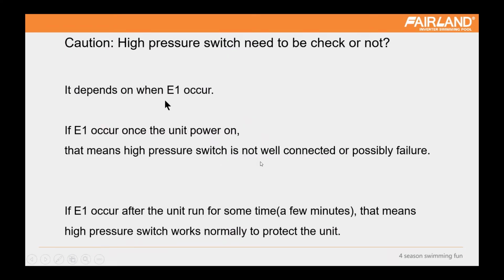So for E1, we have a tracking way. You need to track when E1 happens. If E1 is displayed once the unit powers on, that means the problem is from the hardware parts: the high pressure switch, the integrated board, and the wire connection between them. And if E1 displays after the unit runs for some minutes, that means the high pressure switch works normally to perform its protection function. So normally the problem is from the water flow volume or maybe the installation space. Most of the time it's a water issue.